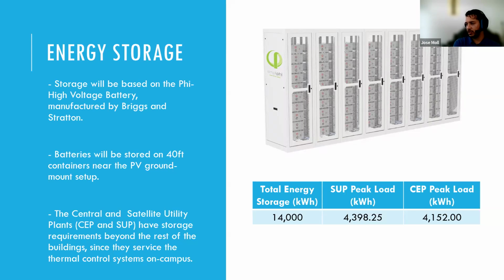With set peak hours and peak consumptions available on screen, we sized the energy storage system to be able to handle around an hour and a half to almost 2 hours, depending on the configuration. This limited energy storage system was really determined by the university's main goal, which was to have a cost-effective system and to maximize their energy offset, meaning how much energy they save by consuming from their PV production instead of from the peak utility rate.